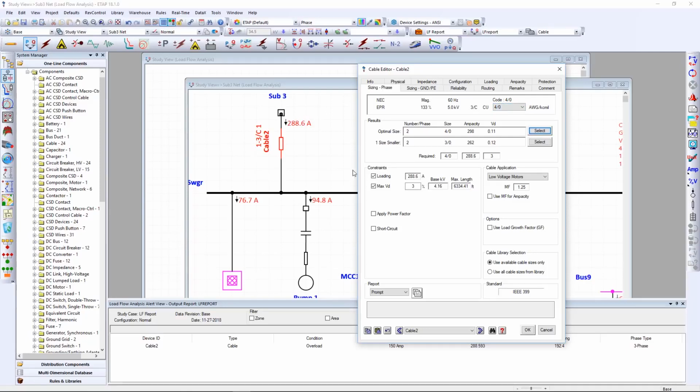A lot of times the equipment, when we're doing sizing, we have to take into account 100% loading for motor loads, and in fact, when you're sizing an MCC, you typically would want to use also the multiplication factor for ampacity, which is 125% of the largest motor on the MCC. We're not sizing an MCC for this particular case, but that option is also available.